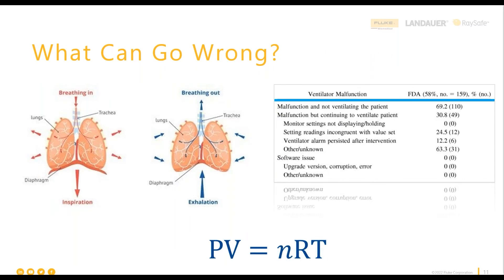I want to hit on the interdependency between all those parameters. Those relationships are defined by the ideal gas law and Boyle's law. The ideal gas law shows the effect that a change in temperature would have on either pressure, volume, or both — an increase in temperature causes an increase in pressure, volume, or both, and vice versa. There are relationships between gases that are really important to understand.